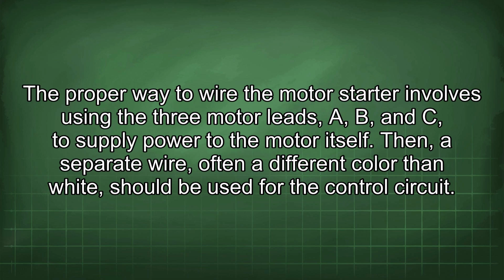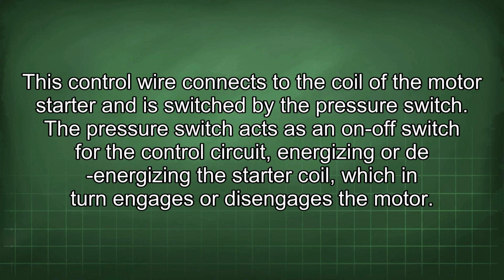The proper way to wire the motor starter involves using the three motor leads, A, B, and C, to supply power to the motor itself. Then a separate wire, often a different color than white, should be used for the control circuit. This control wire connects to the coil of the motor starter and is switched by the pressure switch. The pressure switch acts as an on-off switch for the control circuit, energizing or de-energizing the starter coil, which in turn engages or disengages the motor.